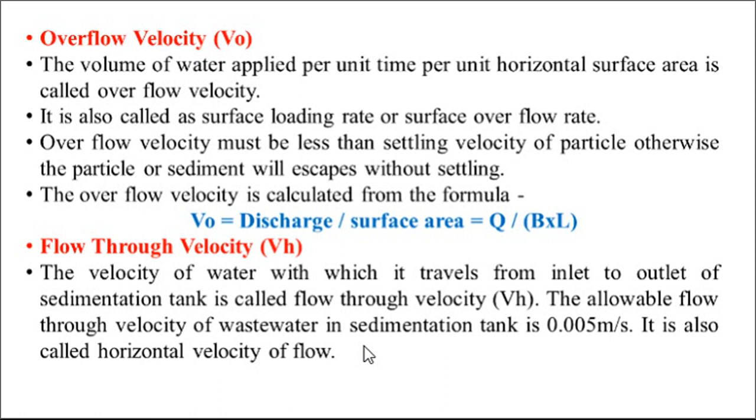Overflow velocity must be less than settling velocity of particles, otherwise the particles or sediment will escape without settling from the sedimentation tank. The overflow velocity is calculated from the following formula, that is overflow rate is equal to discharge divided by surface area of that tank, or Q divided by B into L.